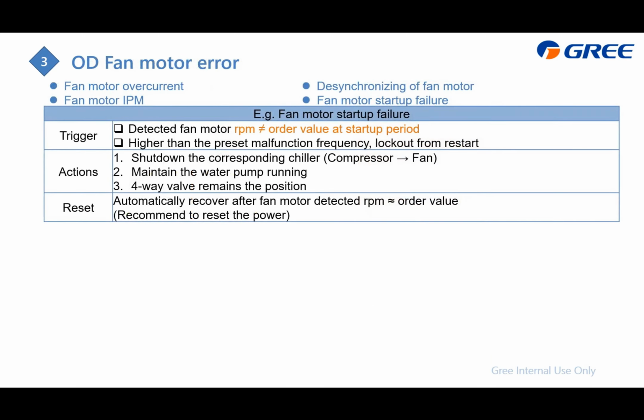And then the next is the outdoor fan motor error. The fan motor is similar to the compressor, except there's no oil return system. So the judgment and also the errors are very similar, including fan motor overcurrent, fan motor IPM, and also desynchronizing and start-up failure. This is when we detect that the fan motor RPM is not the same as our order, especially at the start-up period. We will also trigger this error.